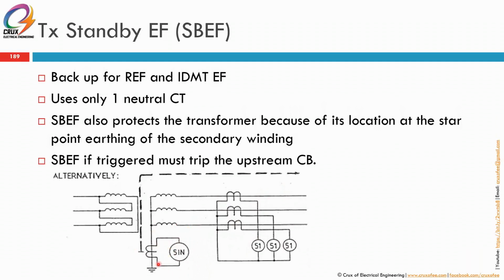So what happens is this relay will pick up 51N standby earth fault, but it needs to trip the upstream breaker. There's no use tripping only this breaker, because even if you trip the breaker on the secondary, the fault is still there. So you need to trip the secondary breaker as well as the upstream breaker. Okay. Standby earth fault, if triggered, must trip the upstream circuit breaker as well.